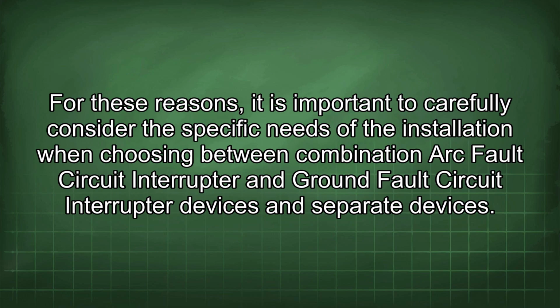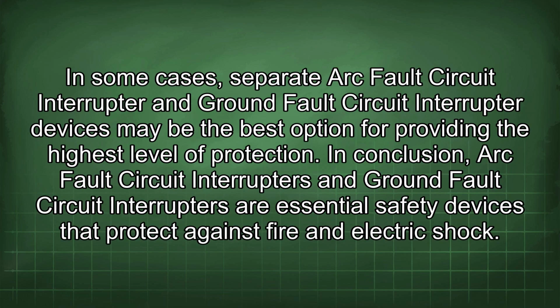For these reasons, it is important to carefully consider the specific needs of the installation when choosing between combination devices and separate devices. In some cases, separate arc fault circuit interrupter and ground fault circuit interrupter devices may be the best option for providing the highest level of protection.